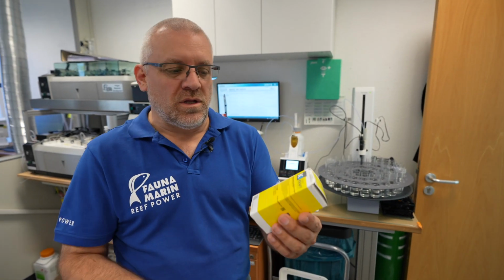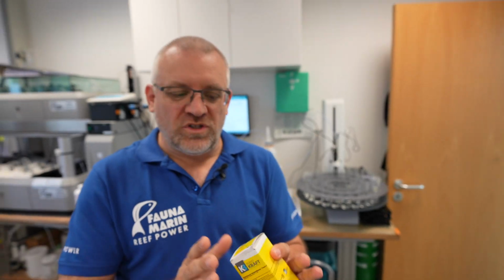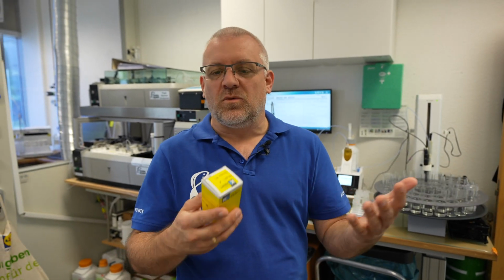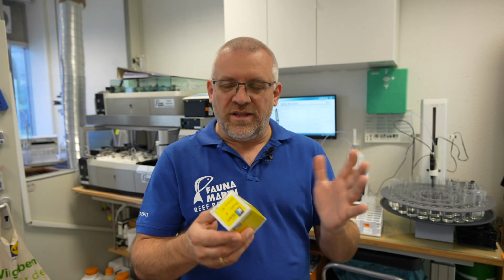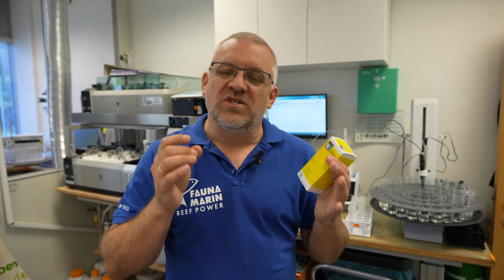In this diluting of the probes, there's a big possibility for mistakes. And it doesn't matter if you do the calibration right or not, because the machine detects properly that the mistake was in the diluting. If it's not the right amount and later you calculate it up, you will have a mistake. The leading labs nowadays use specific NIST standards from companies which make them especially for us. These standards are certified, you get papers for them, and you pay a lot of money. A good standard is about $1,000 for a bottle of multi-element standard. That's why it has to be extremely accurate, and that we use for calibration.